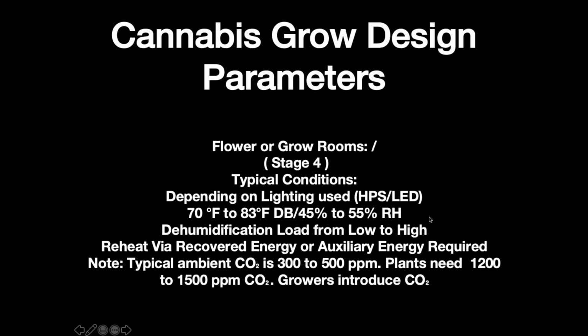And a note here is that when you're working with your grower, it's critical that you get them to tell you the conditions that they're going to be looking for. One of the jobs that we had, they'd given us 75 and 50% relative humidity. After the job was built and installed, they came back and said, well, we really want to run it at 70 and 50% relative humidity. The equipment was undersized and we couldn't get to that condition. So you've got to make sure that the grower gives you all of that information.